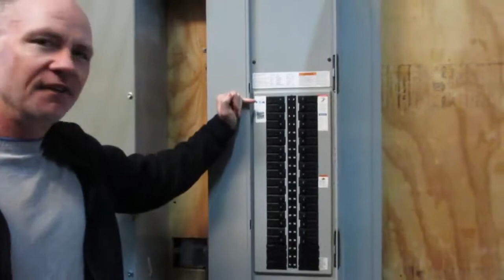We've got two 1200 amp three-phase circuit breakers. We've got the rotating machinery, the fans, running off the three-phase. Each of those goes to a 400 amp panel where we pull single phase 208 volt 30 amp off each of the connections.